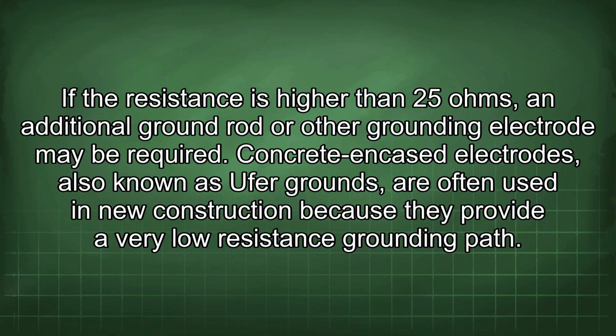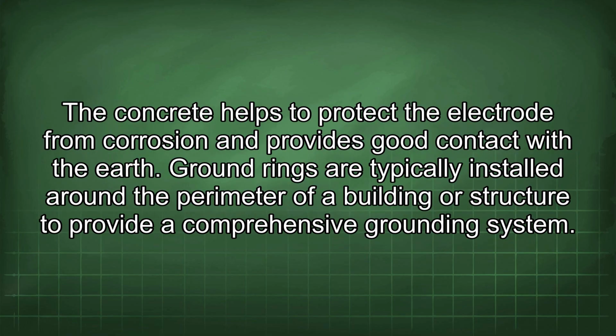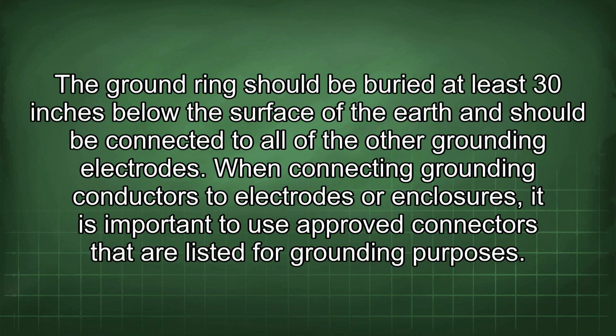Concrete encased electrodes, also known as Ufer grounds, are often used in new construction because they provide a very low resistance grounding path. The concrete helps to protect the electrode from corrosion and provides good contact with the earth. Ground rings are typically installed around the perimeter of a building or structure to provide a comprehensive grounding system. The ground ring should be buried at least 30 inches below the surface of the earth and should be connected to all of the other grounding electrodes.